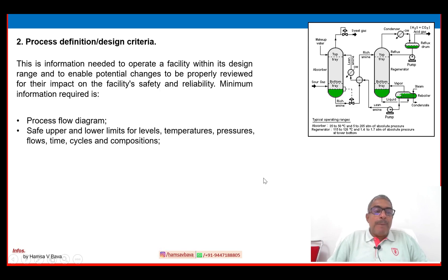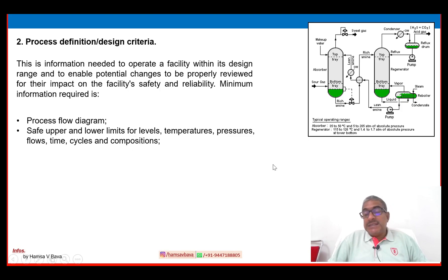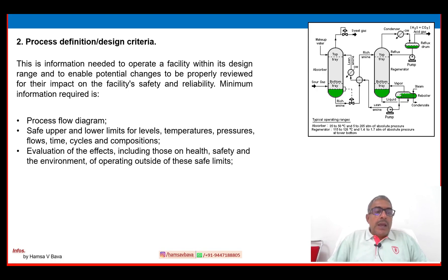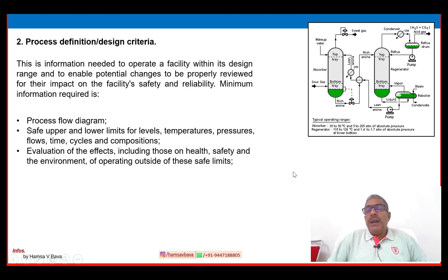The safe upper and lower limits of level, temperature, pressure, flow, time, cycle and composition are also required. Some PFDs may provide that information, and others may not — but the P&ID drawing can provide these details, covering process variables such as level, temperature, pressure and flow, as well as safeguarding and operating parameter details. This also includes evaluation of the effect — including health, safety and environment — of operating outside these safe limits.